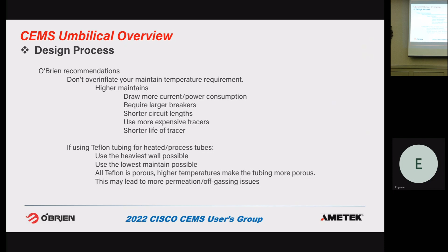And then Teflon tubing. As everybody knows, Teflon is porous. So we want to reduce any possibility of permeation, of getting CO migration through the tube wall. So the two big things are use the heaviest wall. The heaviest wall PFA we use is an 062 wall. We also offer 030, 040, 047, and then 062. Go to the heaviest wall, the thicker wall resists permeation more, and then use the lowest maintain temperature. As that Teflon gets hotter, it becomes more porous and more of a path for CO to migrate through.